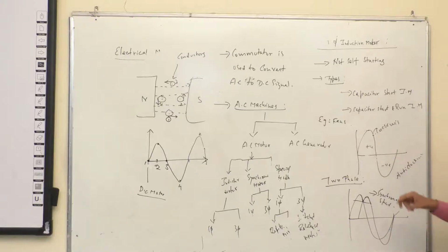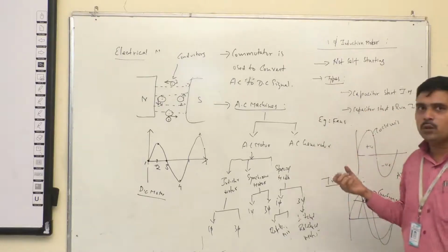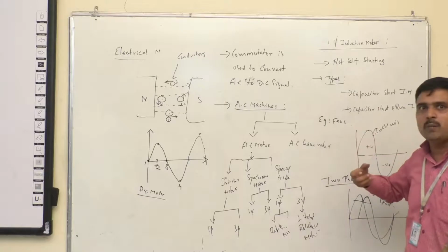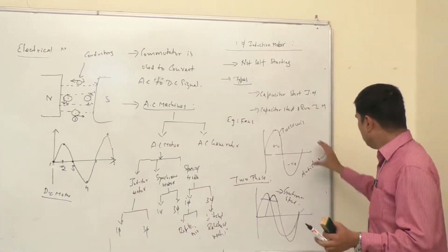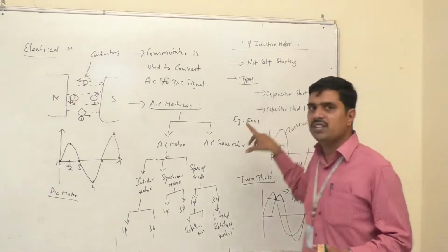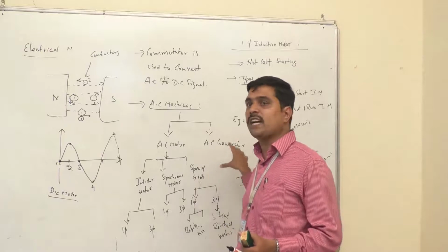In some cases we need to run it at a very high load. Some motors are doing heavy loads, so when you connect it to the load, the speed of the motor goes lower. So we need to connect capacitor start and capacitor run. That means during the running condition also the capacitor is connected to carry that load. That is a single phase induction motor.